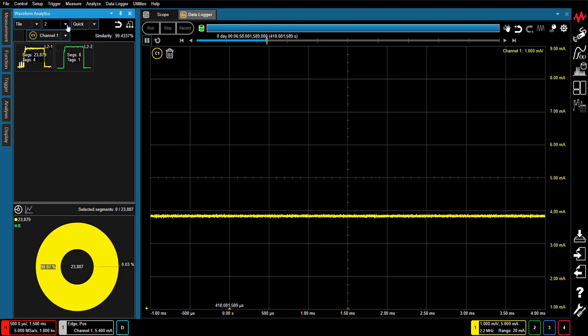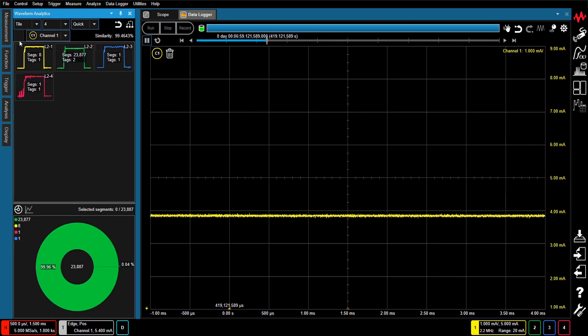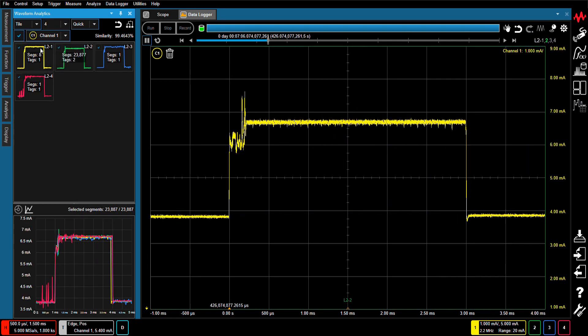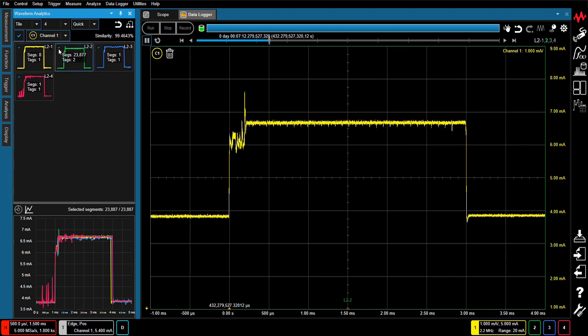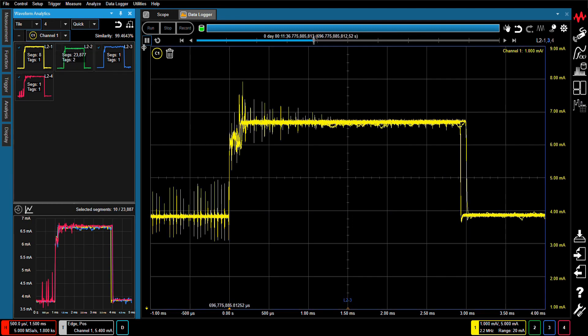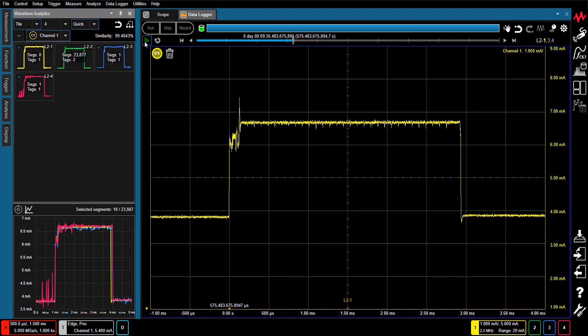You can also select particular waveform clusters and parse them into sub-clusters for further examination. This process can be repeated multiple times to identify more subtle waveform differences. After drilling down two waveform segment levels, you can see that 10 waveforms exhibit anomalies.